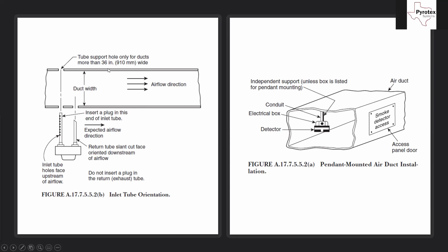Also note: for ducts more than 36 inches wide, you need to drill a support hole on the far side to feed the sampling tube through. For ducts 36 inches or less, just plug the end of the sampling tube. It's important to make sure that end plug is in place — otherwise the vacuum will draw air from the open end sticking out of the duct instead of from the perforated intake side, and you won't get an accurate air sample. The plug forces air to enter only through the perforated side.